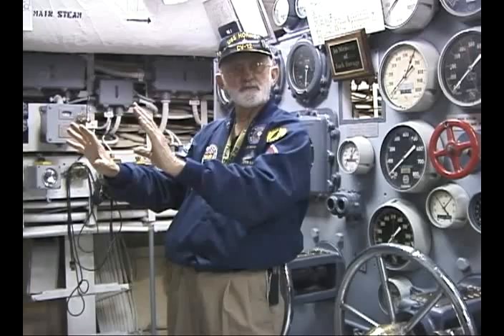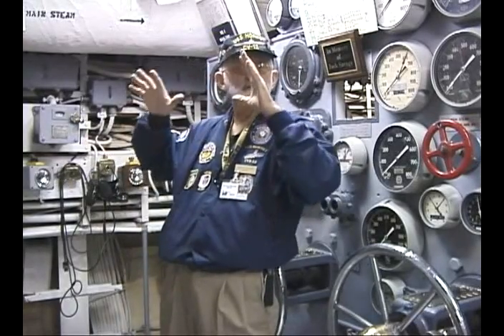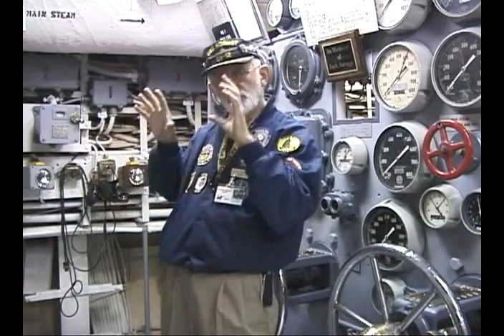They're increasing the fuel oil service pressure at the face of the boiler to get more oil into the boiler to be burned. They're increasing the speed of the forced draft blowers to blow more air into the boilers so you don't make smoke. If you don't have enough air, you smoke black. If you have too much air, you smoke white. And those guys are scrambling to get those boilers to generate substantially more steam. Now it's going to take several minutes to get that to happen.